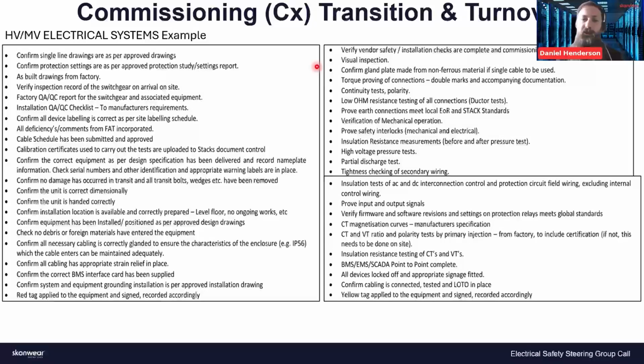If we're following something like this - typically it's a mechanical issue that causes this, because electrical is always great, as we know. Things like torque checking connections, checking those marks, making sure they're in the right place, continuity tests - I think if we're doing those, plus our ductor tests on the bars, if there's good contact you're probably still going to get low resistance, which isn't really going to identify an issue. The mechanical check is your visuals and your torque checking of connections, or pull tests of control cable and things like that.